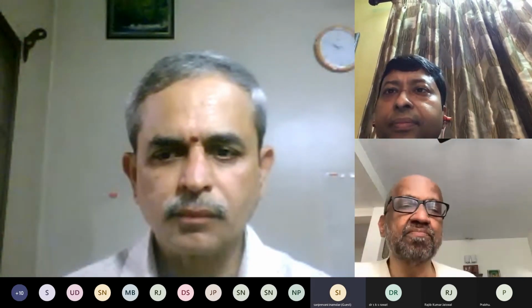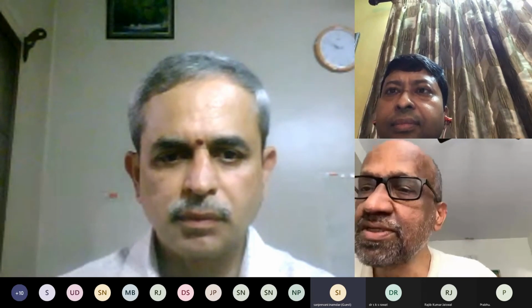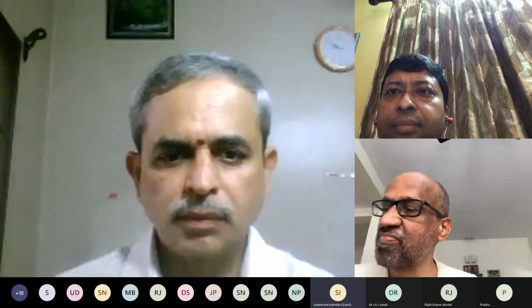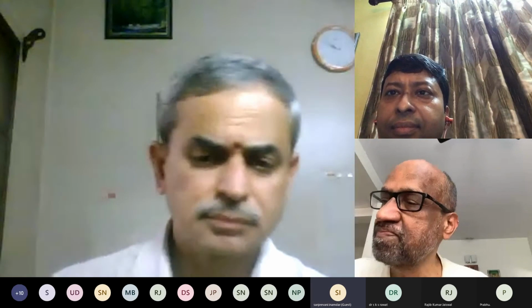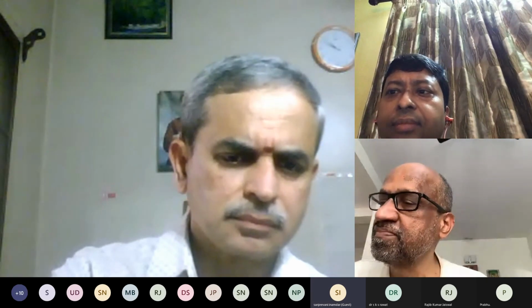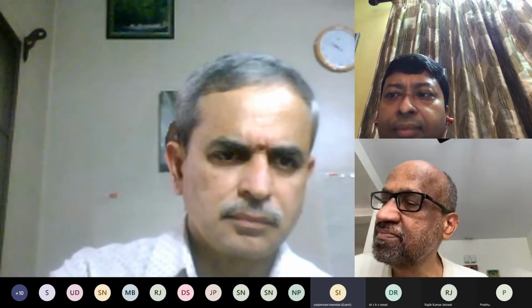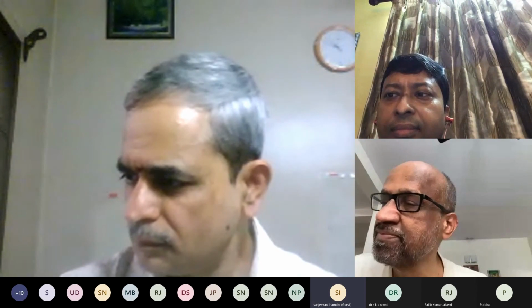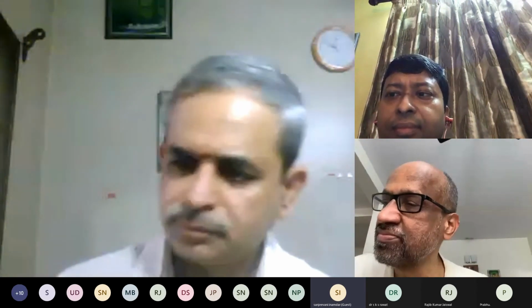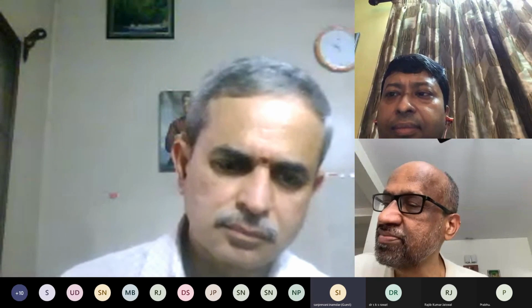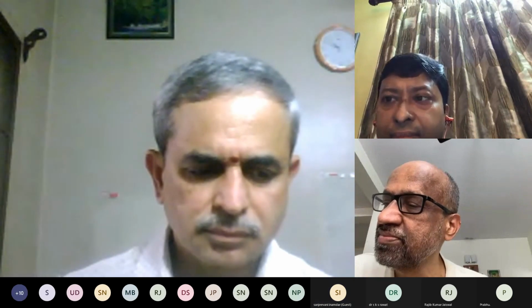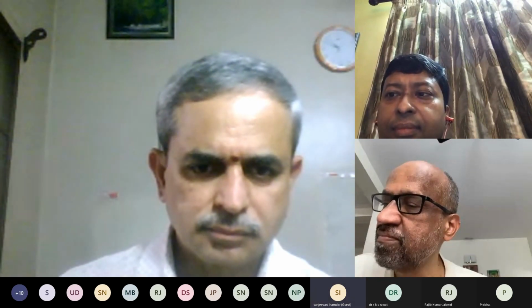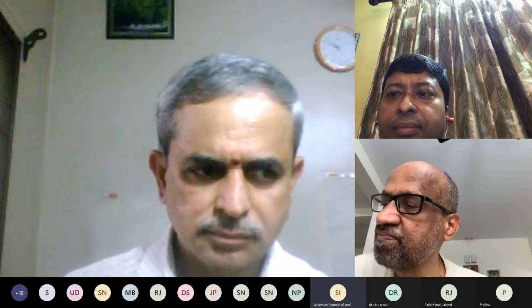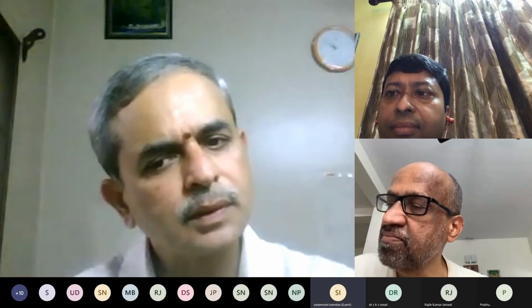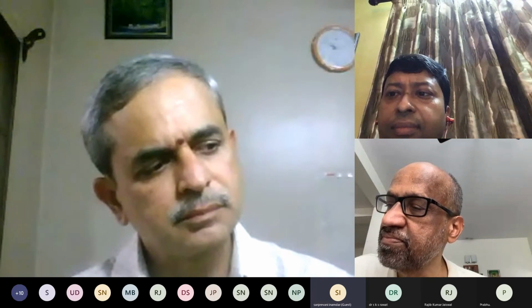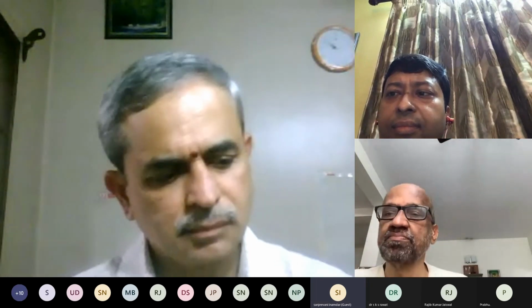Yes. Can I ask one more? See, sometimes when to prevent aliasing, we do lower the baseline or make it higher. Okay, but sometimes it doesn't help. We have seen that. So in this case, it is better to shift to continuous wave Doppler. It happens many times that it doesn't help. It still has that capping effect. So it is better to go to continuous wave to measure that high velocity.